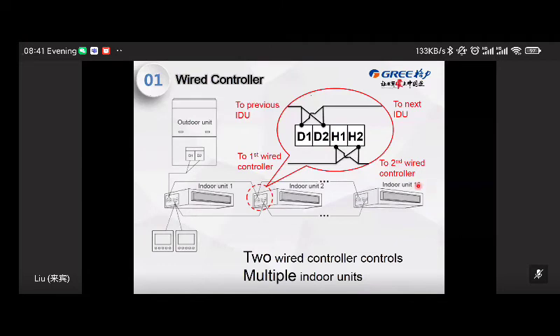This is the double controllers controlling multiple indoor units. It's very similar. One master, one slave, and hook them by the H1, H2 terminal together. And just to remember, the maximum quantity is 16 indoor units. Do not exceed the limit.